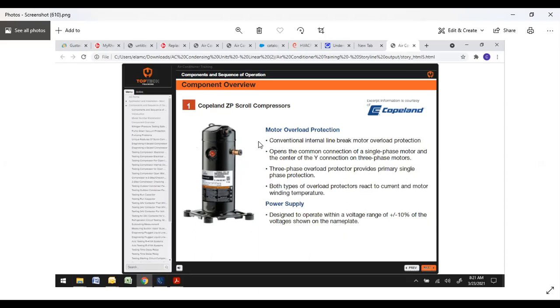Your motor overload protection provides conventional internal line break motor overload protection. What it's going to do is open up the common side of your single phase motors and the center of the Y connection on three phase. So if you have an overheated compressor and you start ohming your windings out in your compressor from your contactor and your capacitor, you'll end up with two open windings. And then if you reach in there and touch your compressor, chances are it's going to be extremely hot. If it's really, really hot and your windings are open, get your garden hose out, start cooling it down. Usually if you concentrate right through here, towards the top, it doesn't take long to get them to reset.